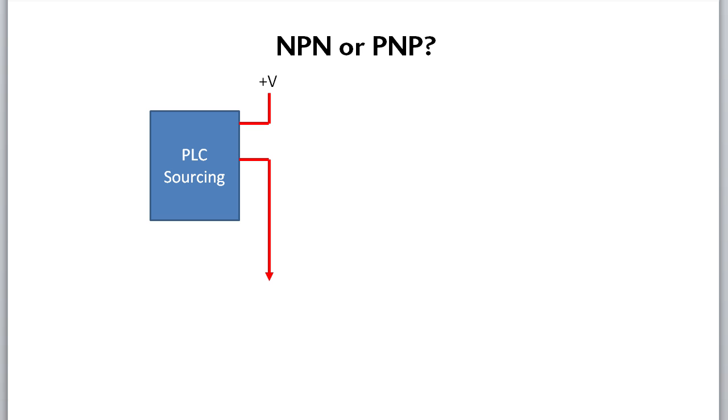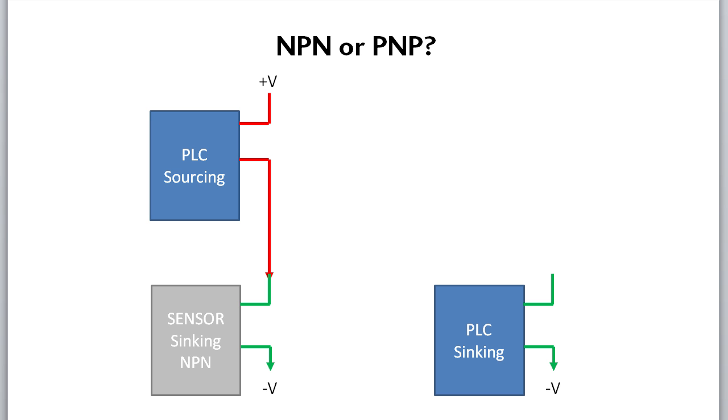If the PLC is sourcing current from the positive supply, then the sensor must be sinking current to the negative supply. If the PLC is sinking current to the negative supply, then the sensor has to provide the source of the current from the positive supply. How do you remember which is which?